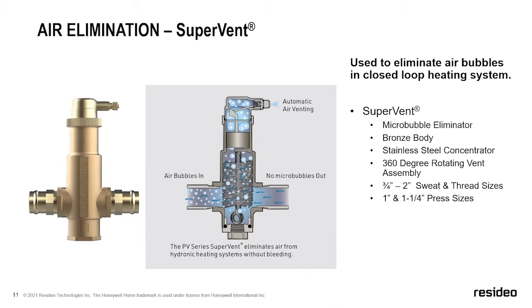It's very, very important to use something that's effective at this type of air collection with modulating and condensing boilers, because they have much less water in them than the old cast iron boilers we used to see. So today we offer these in 3/4 inch through 2 inch, and we are expanding the product offering to offer 1 inch and 1.25 inch with press connections in the box. So they're already attached, or we warranty it from press to press on the fittings, but expanding that press offering for the solution.